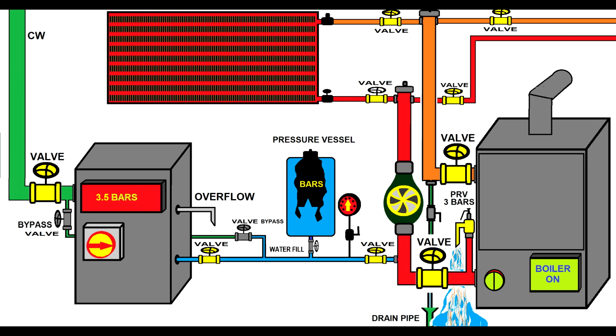You will see now the pressurization unit shows 3.5 bars. And if you look near the boiler, the pressure relief valve, which is a PRV, can support only 3 bars. So because the pressure tried to rise above 3 bars, the pressure relief valve will allow a quantity of heating agent to be evacuated from the system to protect the system against the extra pressure. So that will flood the premises, you will flood the service floor, the plant room, and if the technician does not come in time and is not knowledgeable, once he or she arrives at the premises, they will only observe some water on the floor, because by the time they arrive, the pressure relief valve has eliminated enough quantity to bring the pressure down to 3 bars.